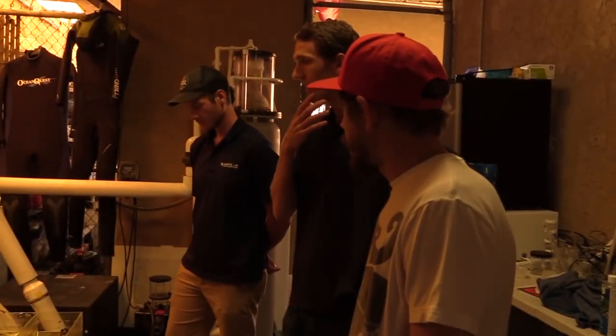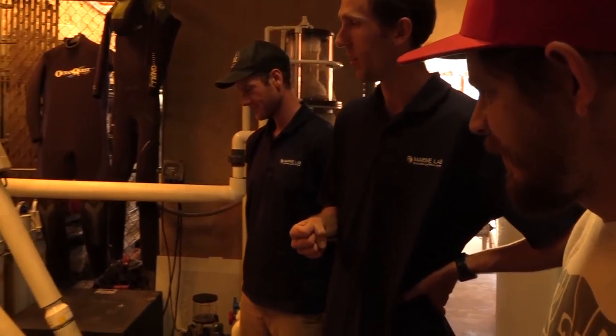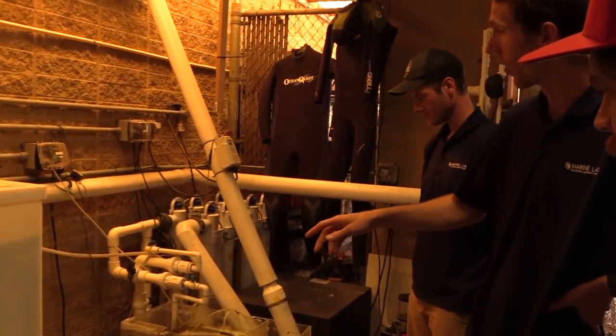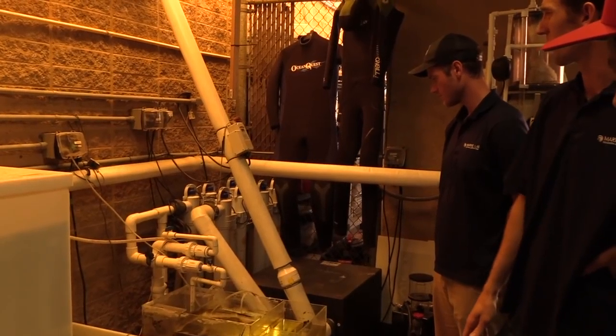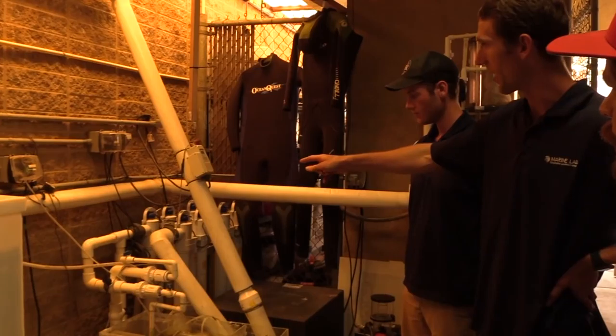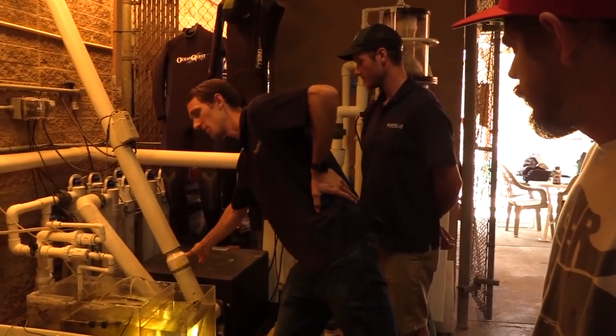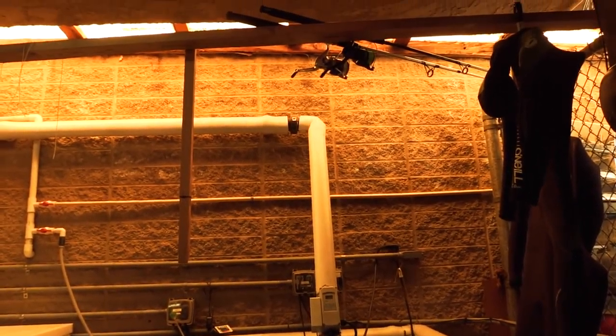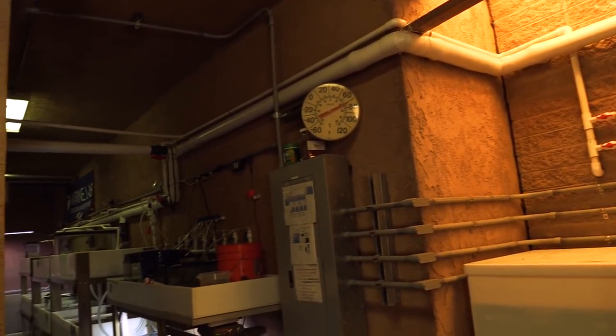This is our life support — it's all custom built. We have a main one-horsepower pump that's sort of hidden in the back there. It circulates our water through our UV sterilizers — we've got eight tubes in line, each 55-watt UV sterilizers — and then from there it runs down into our one-horsepower chiller, up through a check valve to prevent backflow or siphoning from our tanks, and then back up to the tanks. We run our system here at about 16 or 17 degrees Celsius, which is about 60 to 63 degrees Fahrenheit.